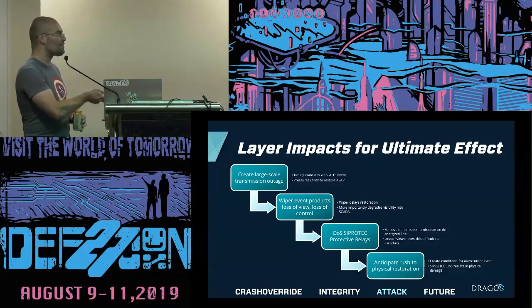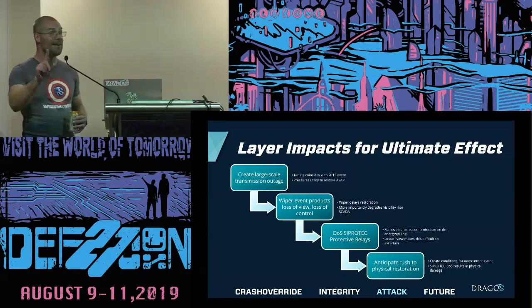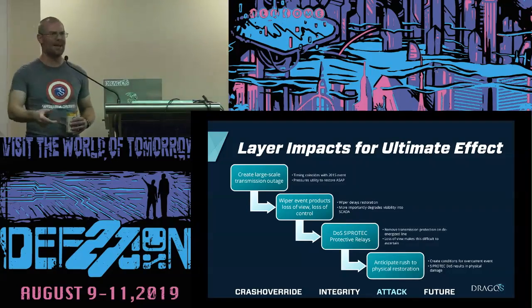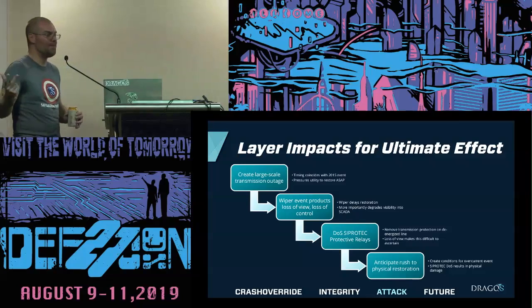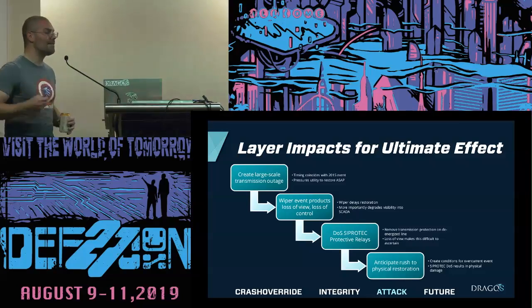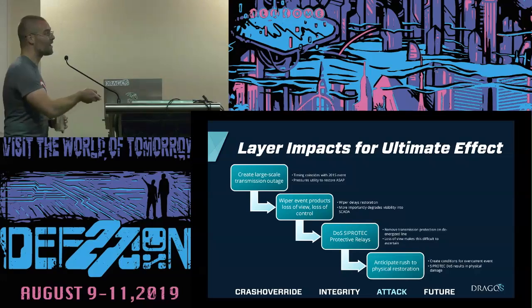So we have this removal of transmission protection on a de-energized line, so the immediate effect is nothing. I have no power flowing through this line, I don't need protection, big deal. But that loss of view makes it difficult to ascertain that that protection is lost.